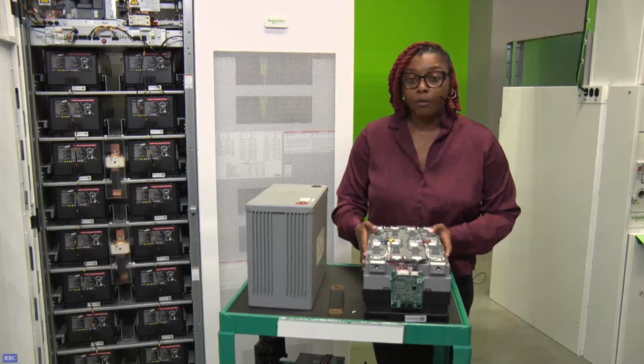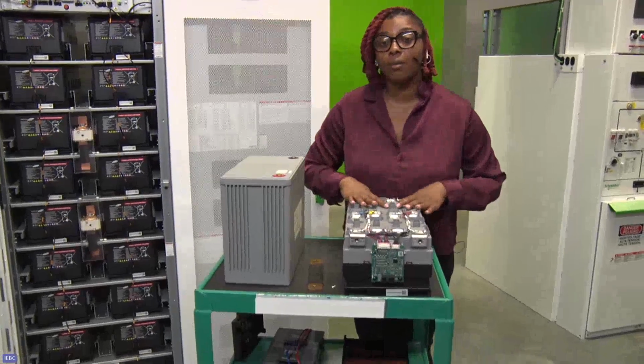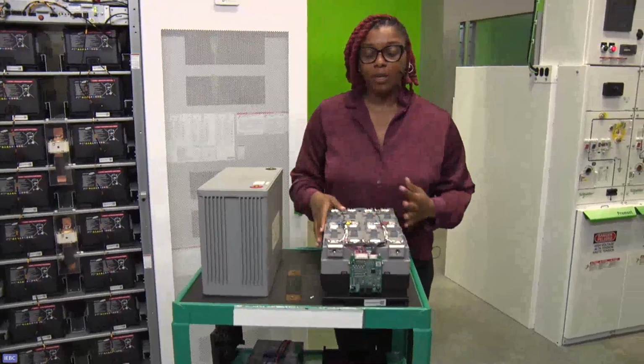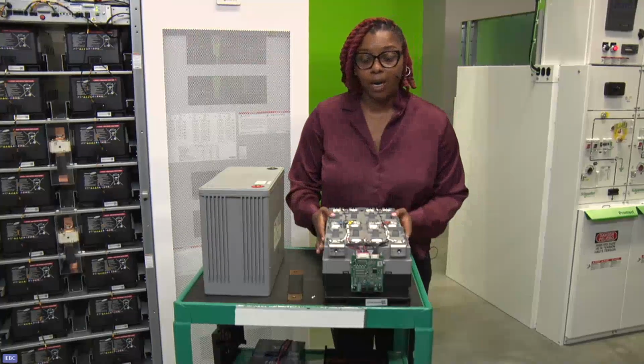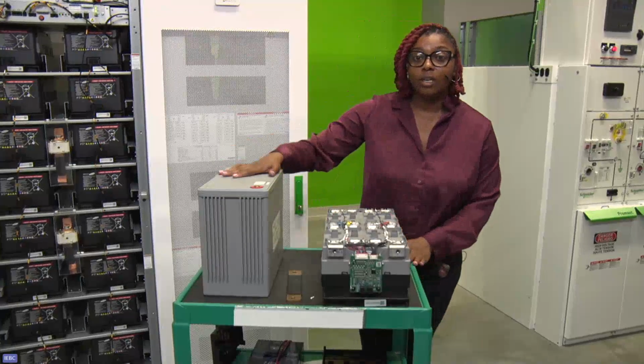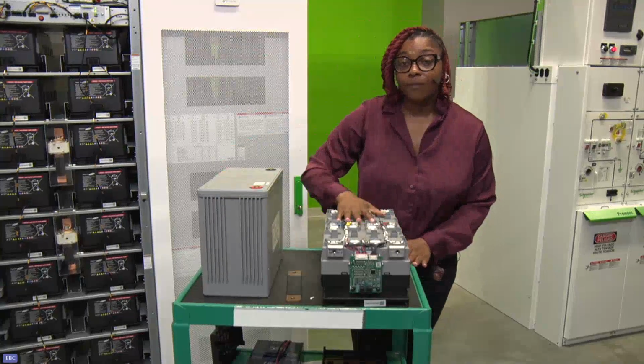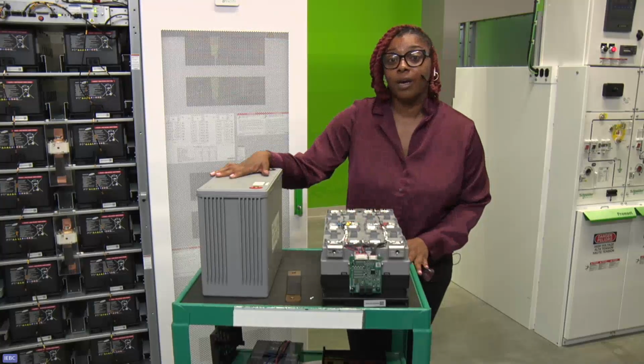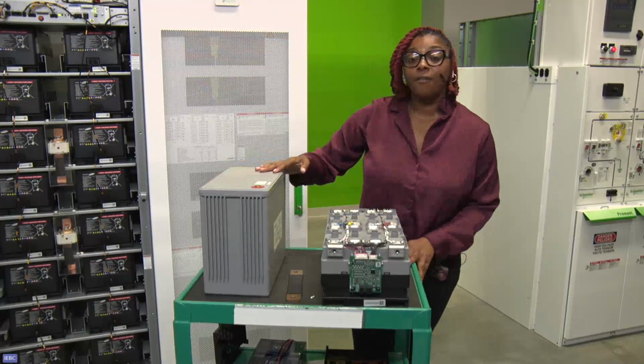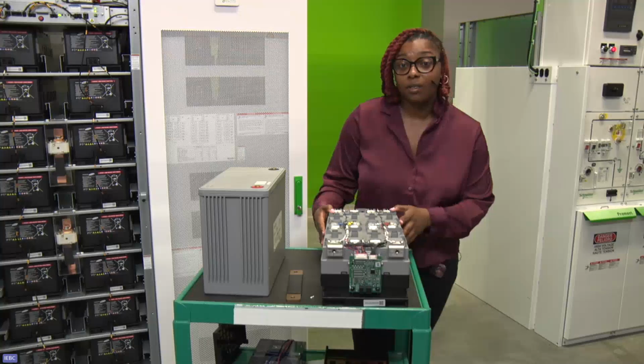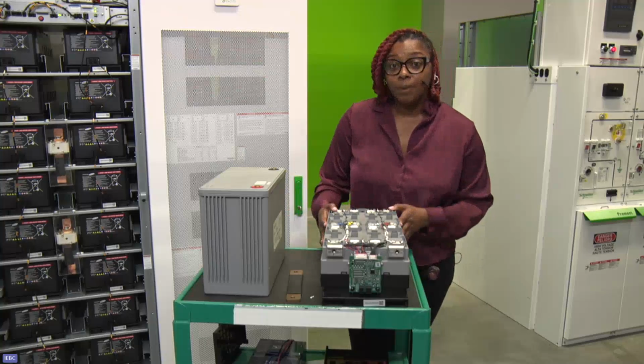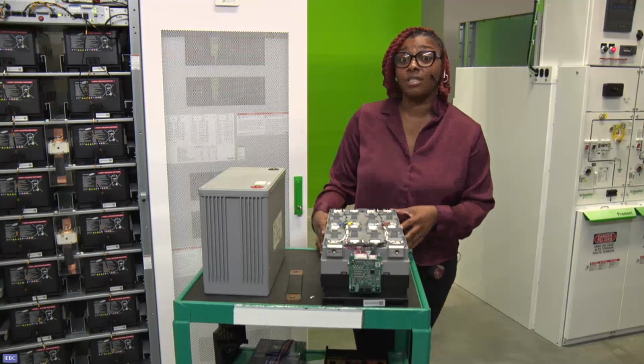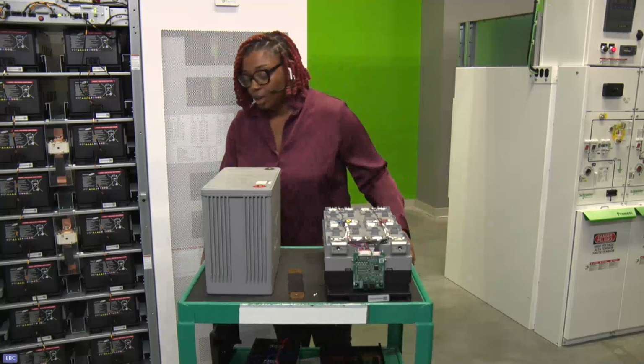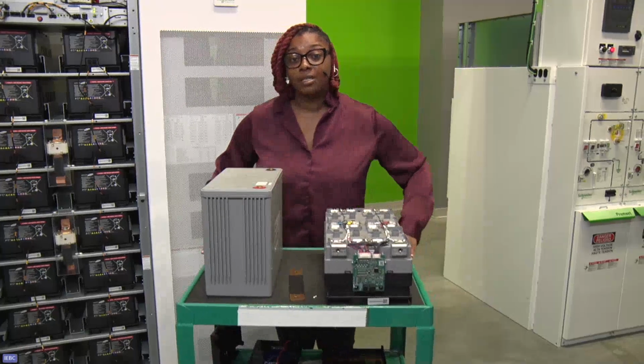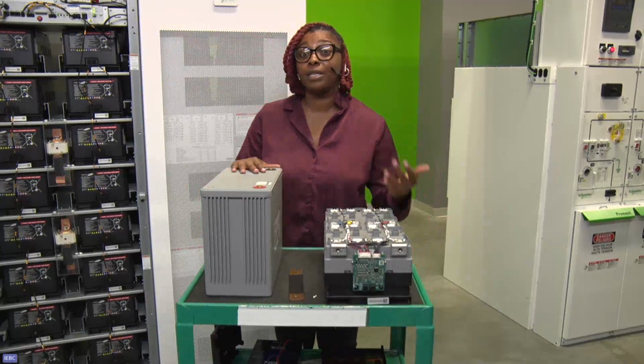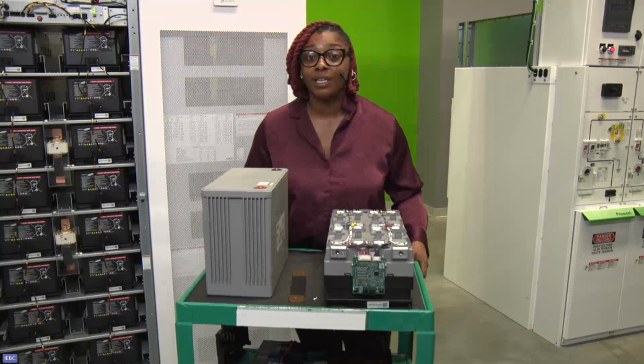What I also want to point out is the comparison between lithium-ion batteries and lead-acid batteries. So again, 16 of these lithium-ion batteries versus 38 of these VRLA batteries. These are 35 pounds to 105 pounds. So we went from about a 5,000-pound cabinet to a 1,500-pound cabinet. Major space savings, major difference in weight. And all of the same benefits between the two, as I mentioned while we were looking at our single phase UPS systems.